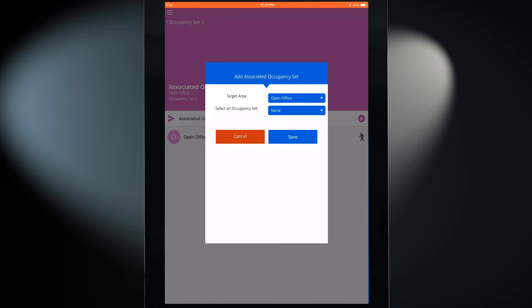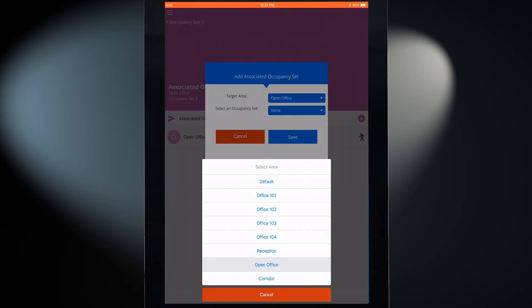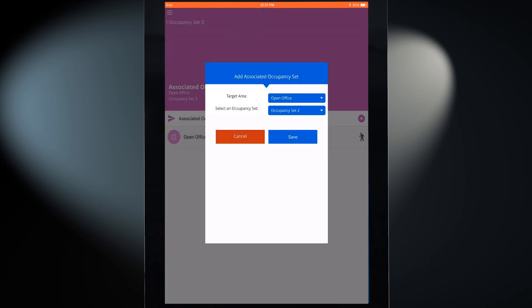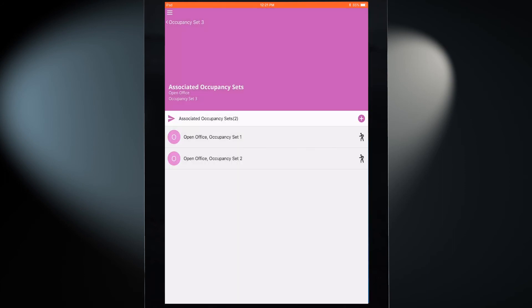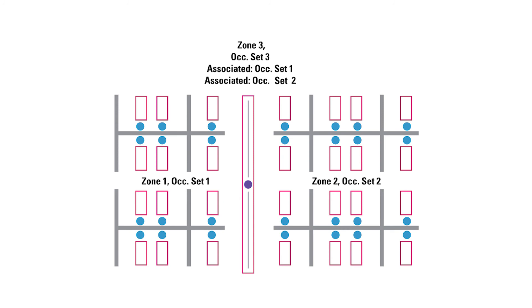Next, repeat the steps to create an additional association to Occupancy Set 2. While cubicle lighting will respond to commands only from sensors within their zones, the walkway zone will now respond to occupancy commands from any sensor in the walkway or cubicle zones.